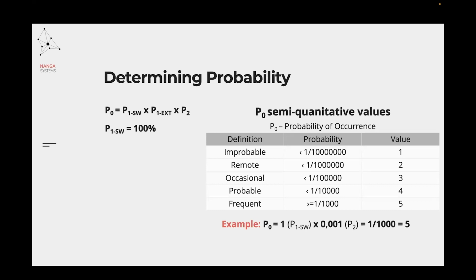In case of the software safety classification, we have to talk about the software itself and external factors. This is why P1 is represented by P1 software and P1 external, where software related P1 is 100%. As an example, if we just take P1 software into account, P0, which is a semi-quantitative value, is going to be a result of P1, which is 100%, multiplied by P2, which in this example is 0.001. In this case, it means that P0 is going to be 1 out of 1000 in terms of probability, which by definition means this is a frequent occurrence. And to describe this with a value, the associated value is going to be 5.